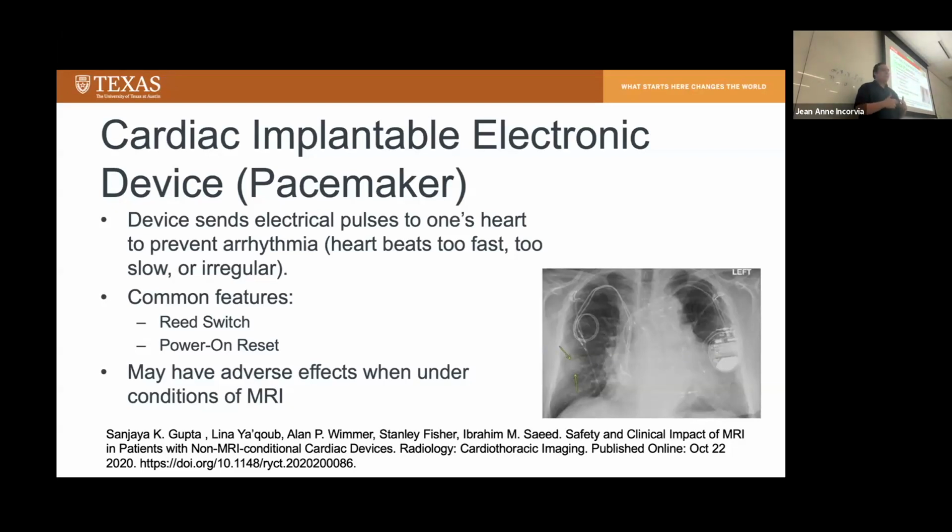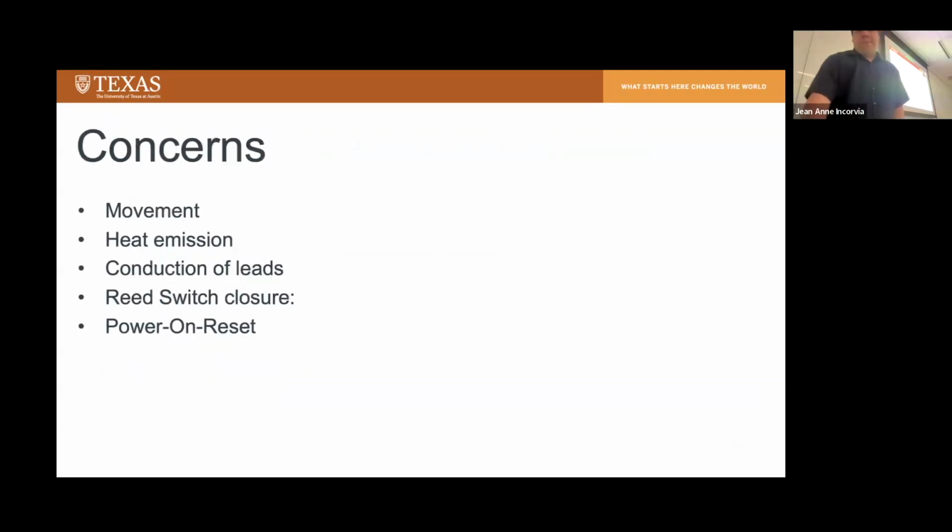factory resets it. The purpose of that is whenever the battery might be depleting or there's some sort of circuit failure within the device itself. So this may have adverse effects when under the conditions of an MRI.